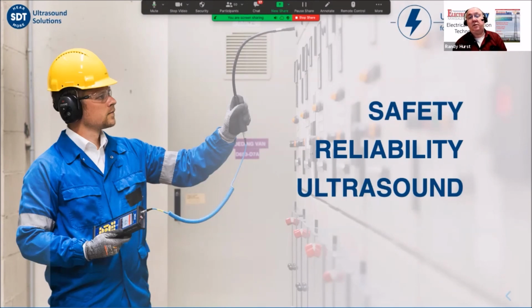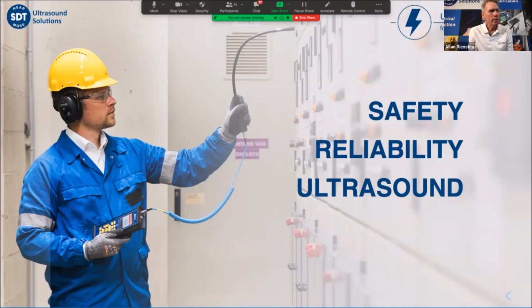Next question: do you have a solution for localization of internal partial discharge in power transformers? No, I'll say there's better technology for that than an airborne detector. We did show an image where we put a magnetic type sensor onto a circuit panel, and we can put that same sensor on an oil filled transformer to hear partial discharge inside, because it uses the oil as the medium to move it from its source inside to the outer shell of the transformer. But honestly, there's got to be better technologies for pinpointing exactly where it is inside the transformer.